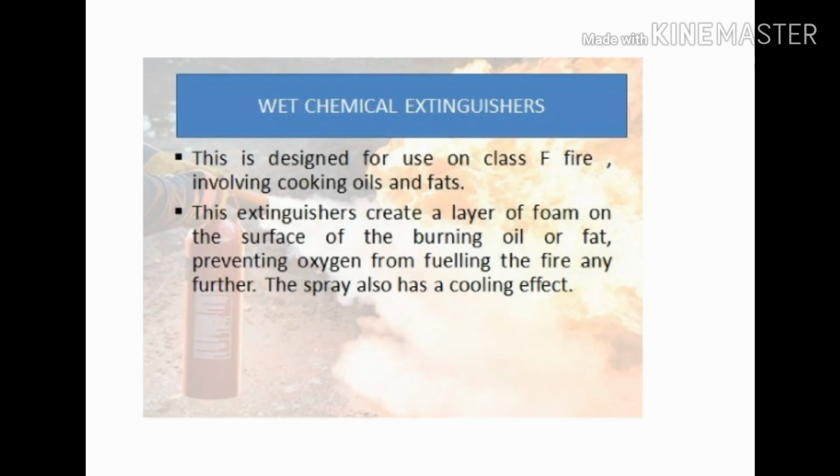Wet chemical extinguishers. These are designed for use on Class F fire involving cooking oils and fats. These extinguishers create a layer of foam on the surface of the burning oil or fat, preventing oxygen from fueling the fire any further. The spray also has a cooling effect.